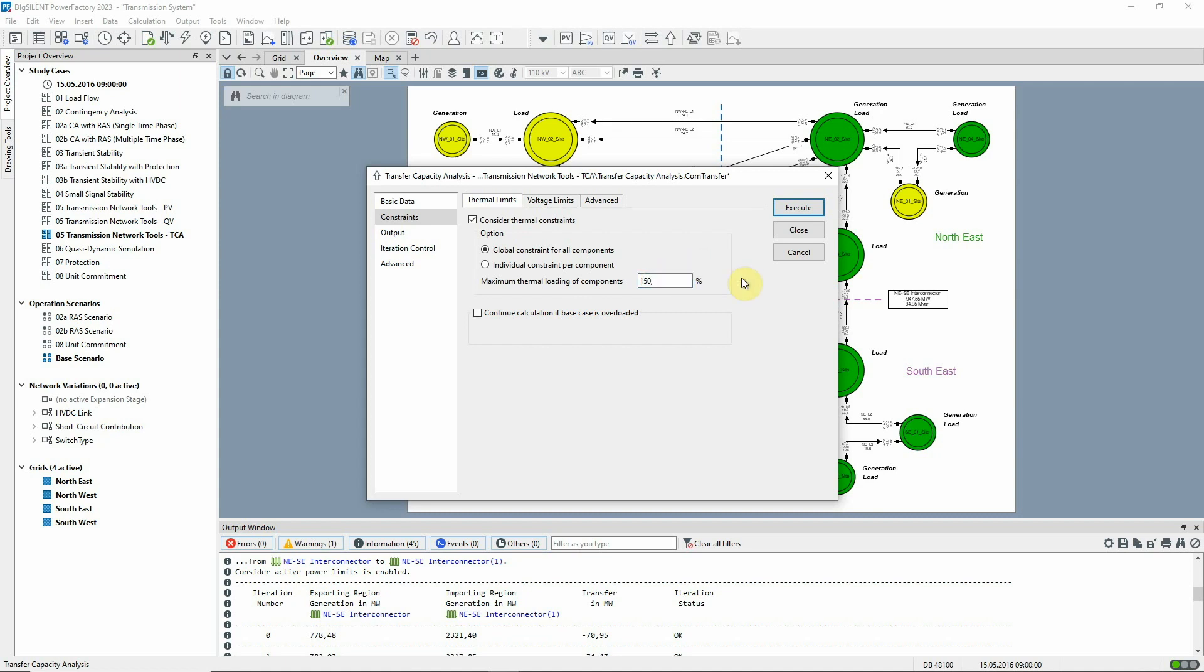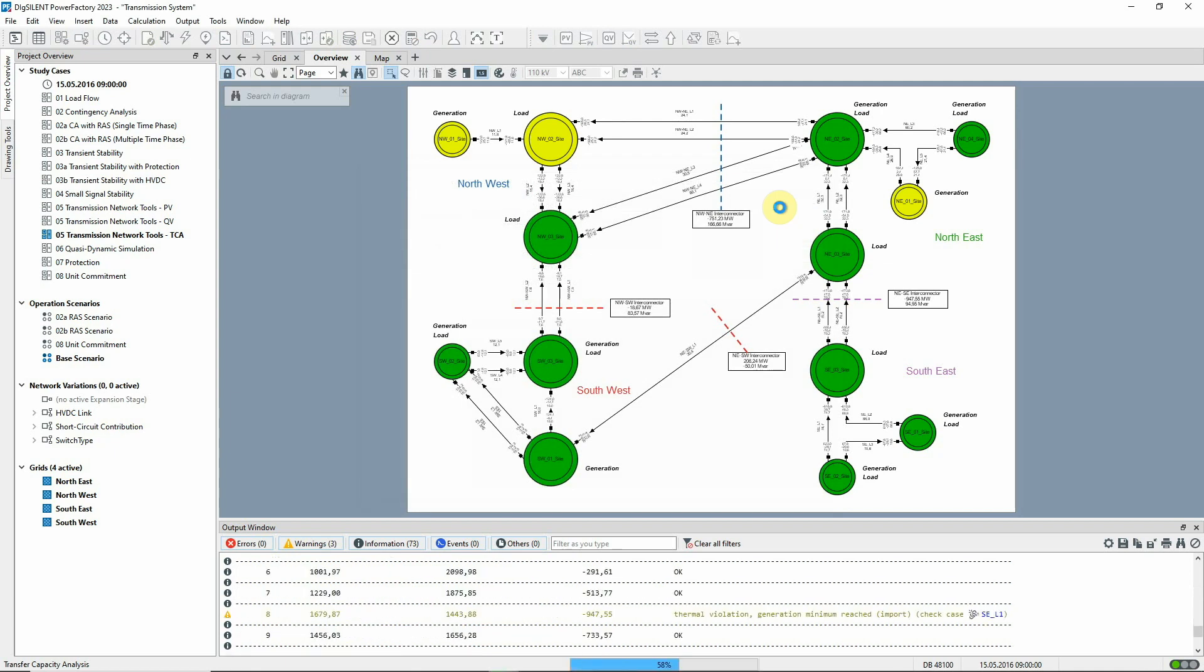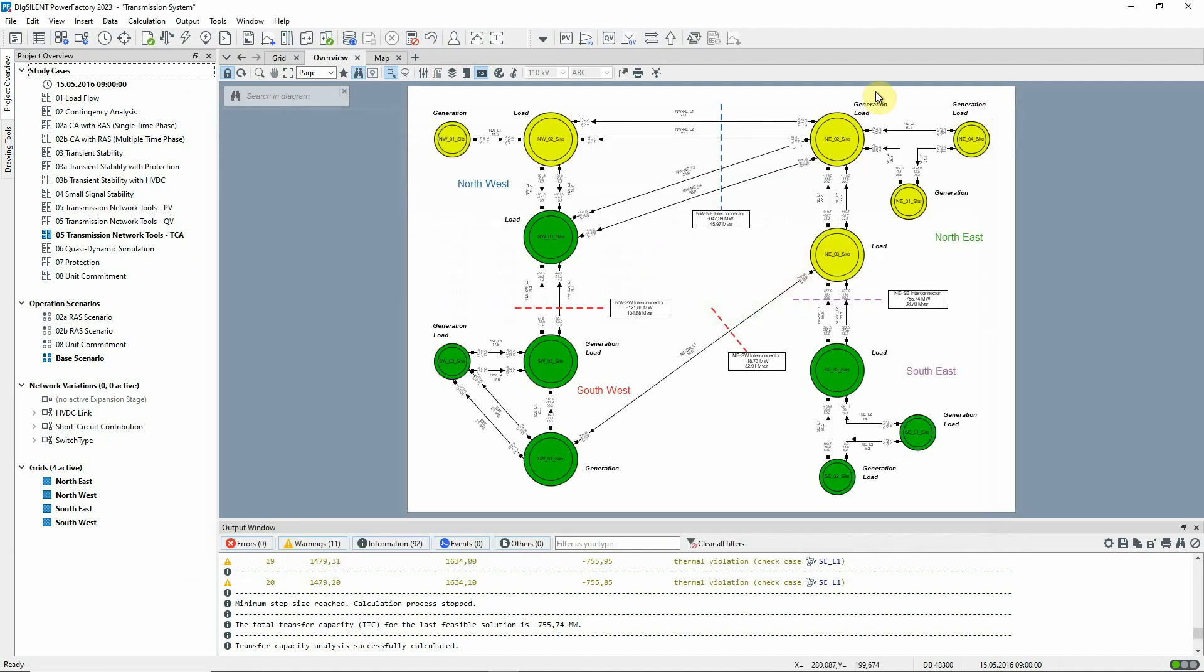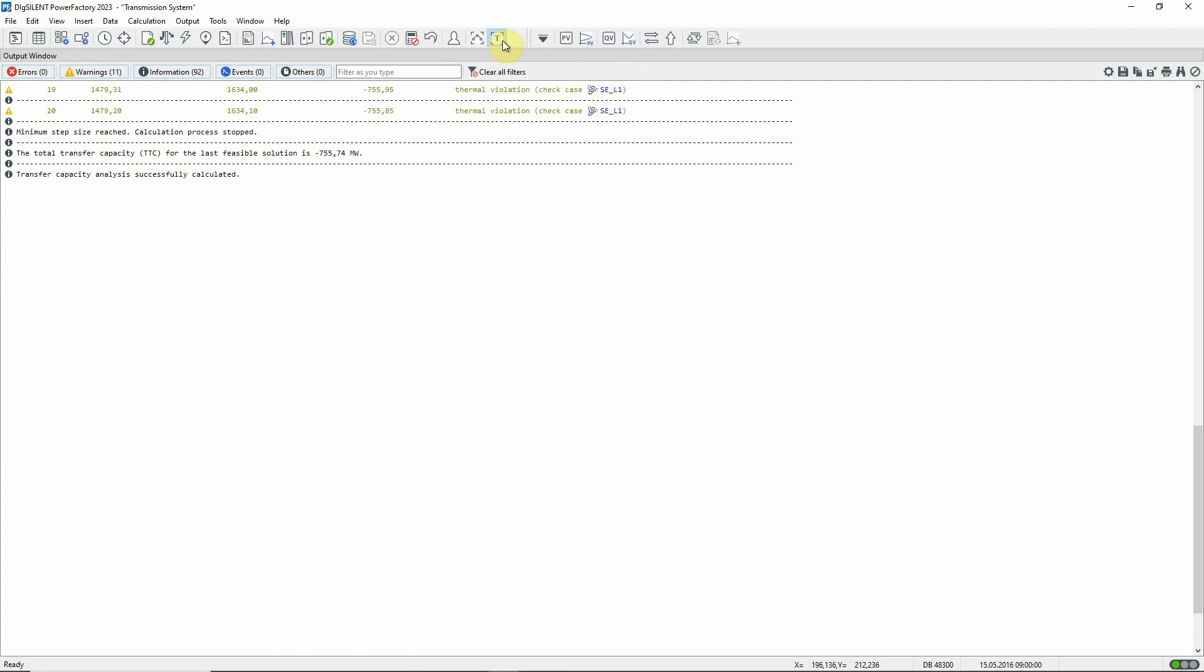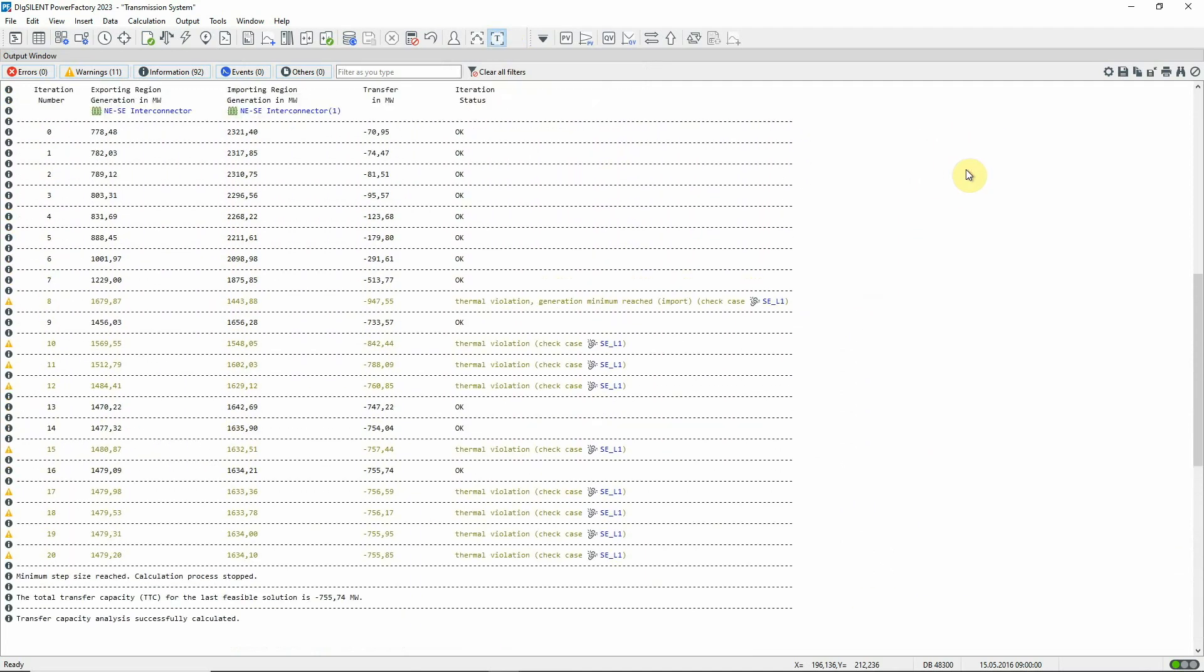The analysis is executed. This report shows the contingency analysis results for the last feasible solution. We can see that the limiting contingency is a fault on line SEL1. And looking at the output window, we can see that the maximum transfer is now about 756 megawatts.